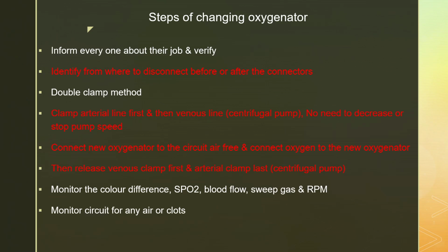As I told you, first, you might see that you have cut the connectors and you are finally left with two tubes opposing each other, so you can't connect them. Then you search for the connectors and that much time is wasted. See here, time is the most important thing. Second, you cut the oxygenator or the components and the tube length has not been kept the same. Then you are struggling. The pump is there, your oxygenator is here, and you are trying to match them. So you have to measure the tube length when you are cutting it, so that you cut it properly. Okay.